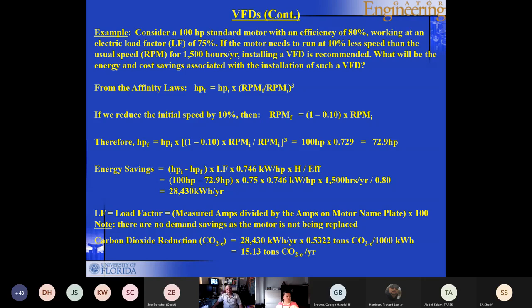If you use the affinity laws, in this case the cube law, the horsepower over the horsepower is proportional to the RPM over the RPM cubed. So the horsepower for the final condition equals the horsepower in the initial condition multiplied by the RPM for the final over the RPM for the initial, all raised to the power 3. So if we reduce the speed by 10%, that means that the RPM for the final is going to be 1 minus 0.1 multiplied by the RPM initial. So you'll end up with 0.9 times the RPM initial. If you cube it, you're going to end up with 0.729 multiplier, which is going to reduce the 100 horsepower motor rating to 72.9 horsepower.